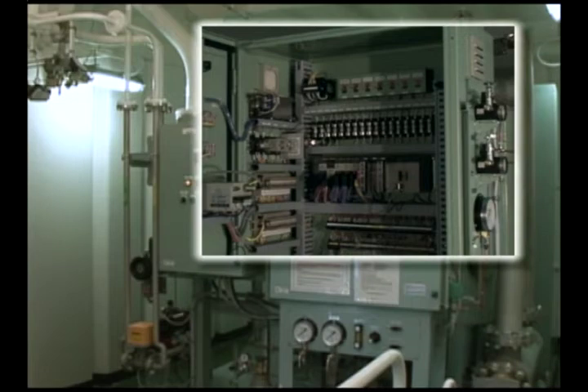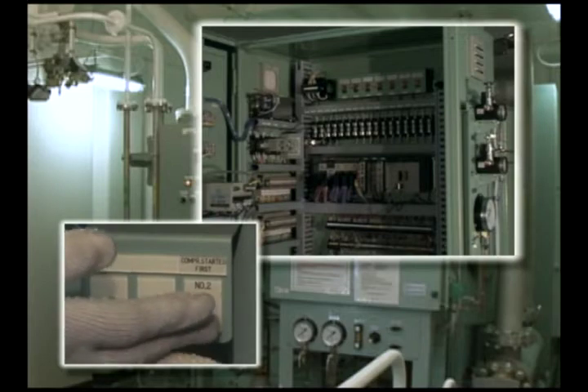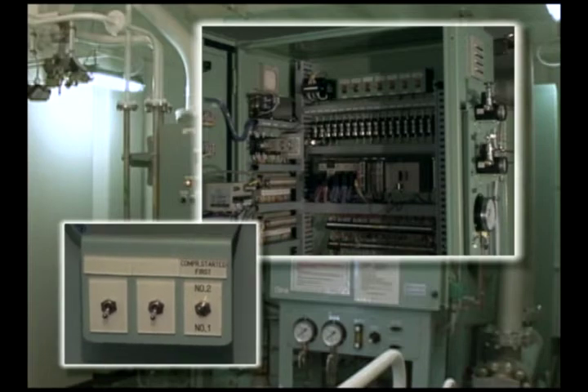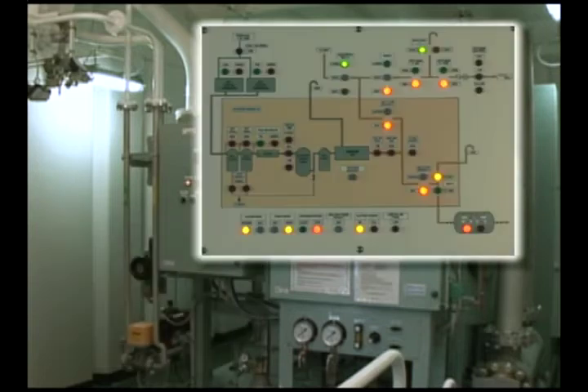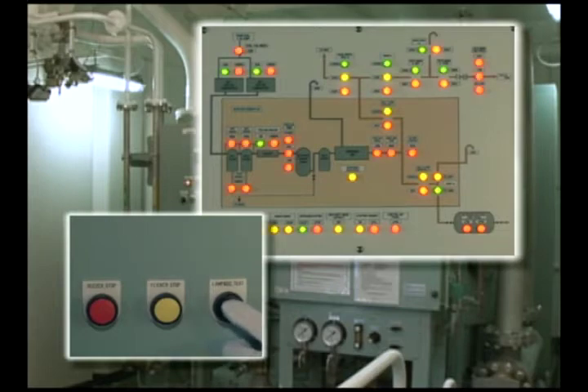Specify the order of activating the compressors on the main control panel. The compressors selected here only run in 99.9% purity mode or 95% purity mode with 50% capacity. Press lamp and buzzer test on the main control panel and each monitor panel to see that all the indicators work properly.